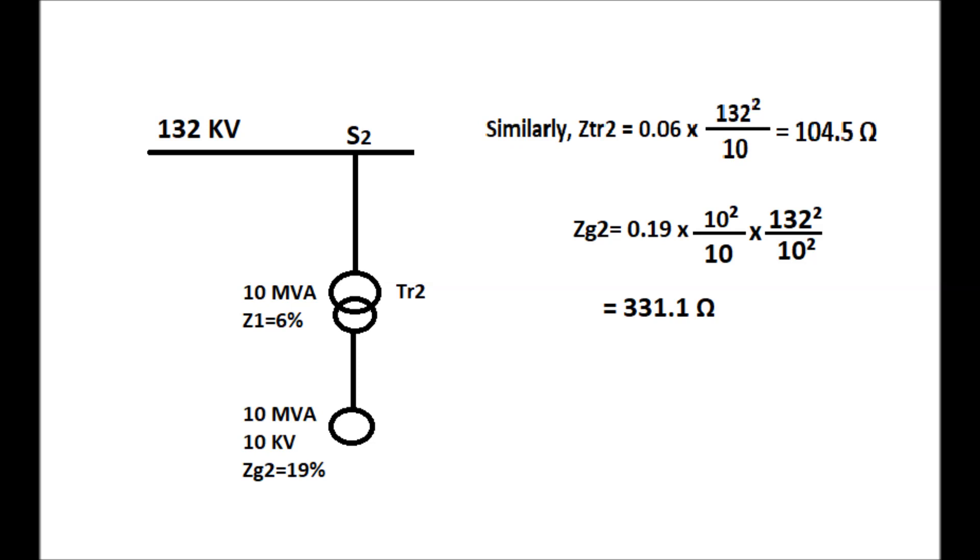Similarly, ZTR2 equals 0.06 times 132 squared by 10, which equals 104.5 ohm. ZG2 equals 0.19 times 10 squared by 10 times 132 squared by 10 squared. That will come to 331.1 ohm.